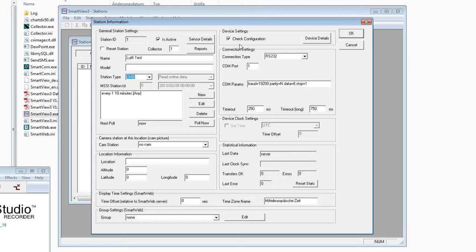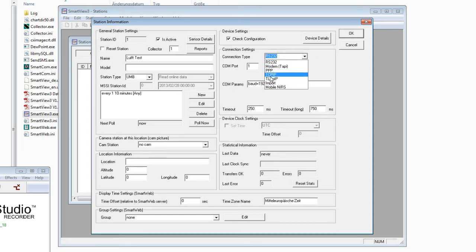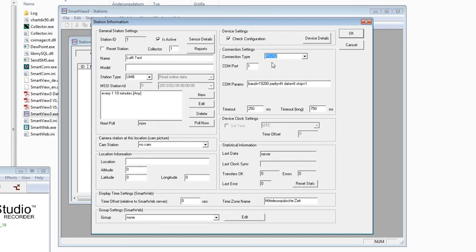The first time you need to read out the configuration and write it into the MySQL database, so you have to use this button the first time only. Then we have the connection settings — we have an RS232 connection here, but you can also choose between modem connection, TCP/IP, TLS over IP, and other options.